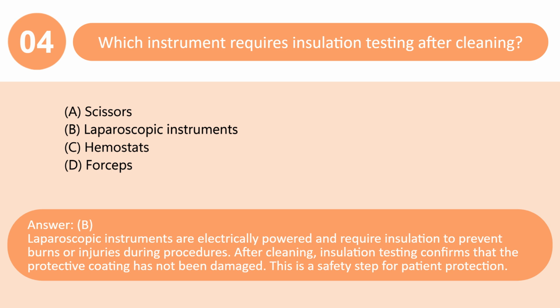Laparoscopic instruments are electrically powered and require insulation to prevent burns or injuries during procedures. After cleaning, insulation testing confirms that the protective coating has not been damaged. This is a safety step for patient protection.